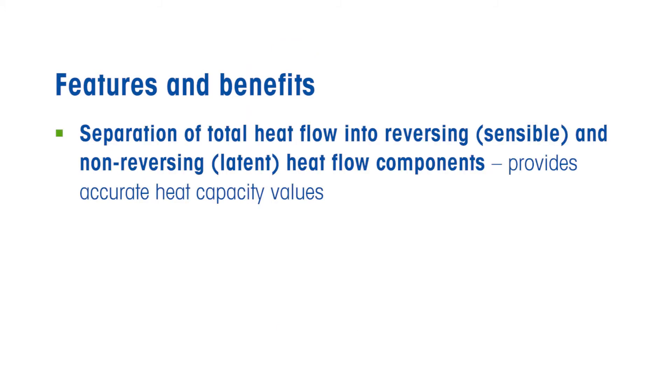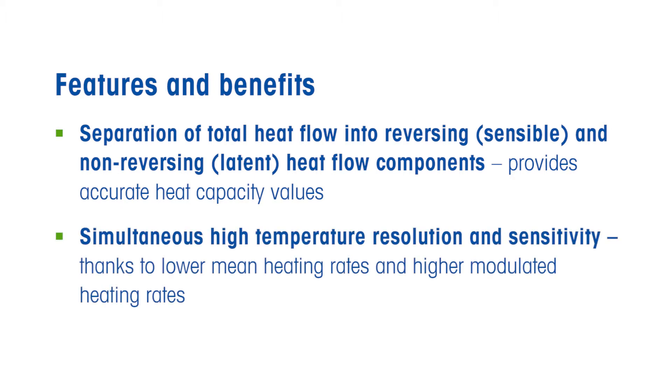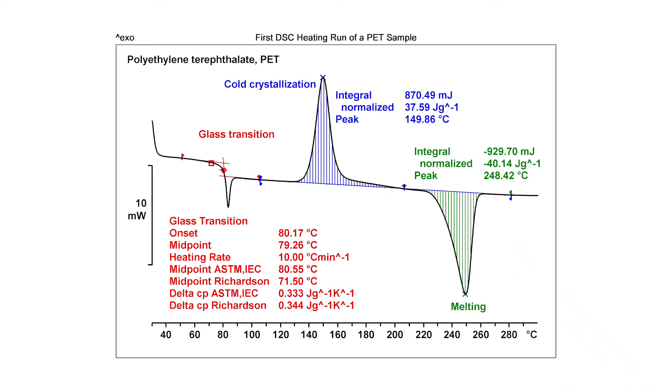ADSC is particularly useful for the separation of superimposed effects. In addition, ADSC measurements permit low underlying heating rates for higher resolution and high modulated heating rates for enhanced sensitivity. For example, the step in the curve at the glass transition is caused by the change in heat capacity of the sample and corresponds to reversing heat flow, while the peak superimposed on the step is due to enthalpy relaxation and corresponds to the non-reversing heat flow.